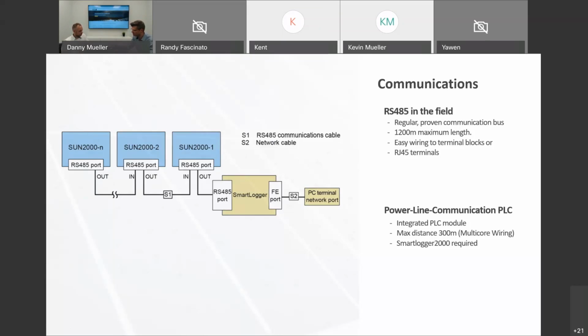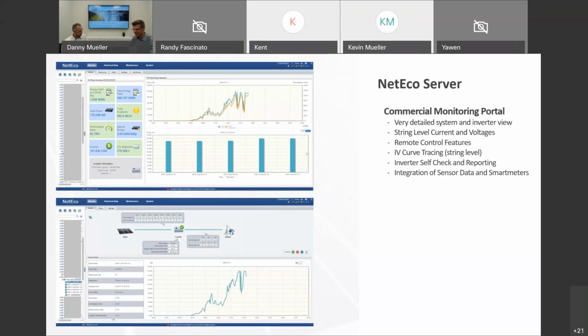Jumping right into, thanks Danny, the NetEco Server. That is the online-based cloud server. We are hosting our own for the Canadian market. And all the data the smart logger will connect is reported and then pushed to that server. And you can log in with your credentials. I've just put in 2 screenshots to not talk too much about the features because it can go very deep. There are a multitude of functions available. You can have just a basic overview of what the system is doing on the top picture, and you can go deep into the detail, for every string, the single string current of every string connected to that inverter. What you get in real time, the data is typically delayed about 2 to 3 seconds, depending on your internet connection on site, and you can live monitor what the system and every single string of the system is doing.